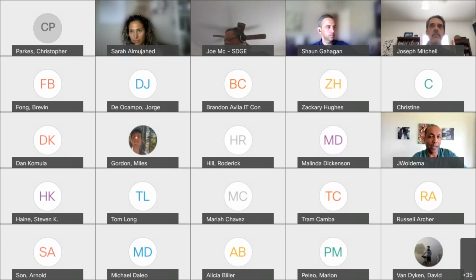My understanding of REFCL, and I'm not an expert, is that it captures a lot, but not all situations, especially phase-to-phase type faults. Covered conductor could address phase-to-phase faults, though it may not cover everything. If there's damage to the covered conductor and a break occurs, a balloon or animal contact there could still cause a fault.